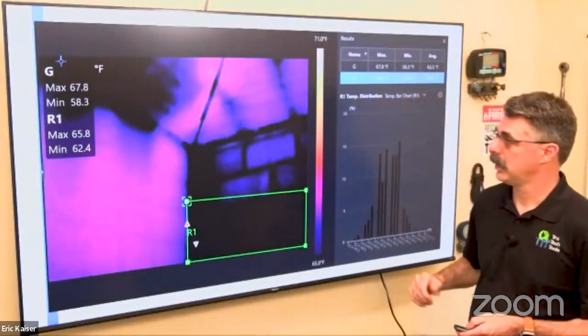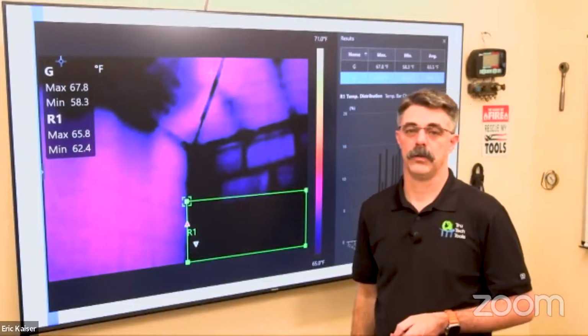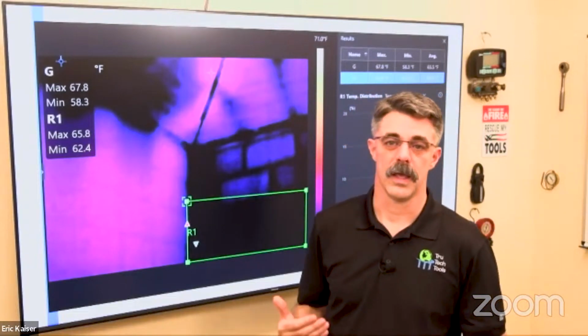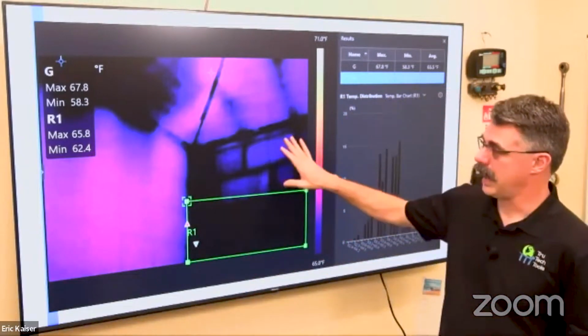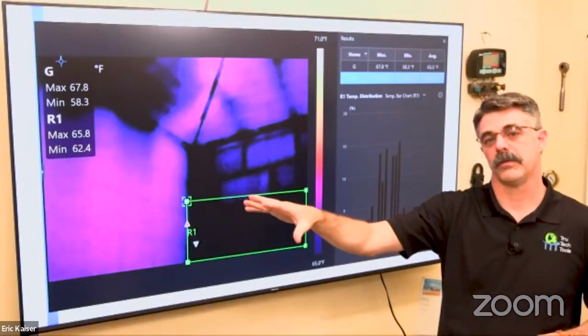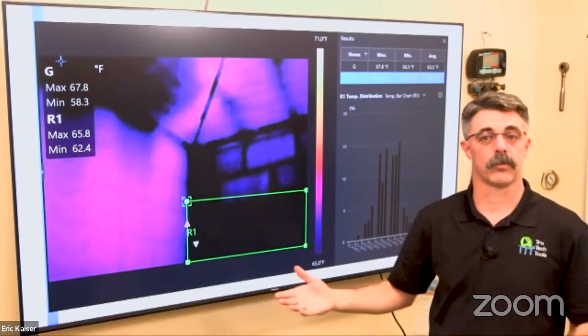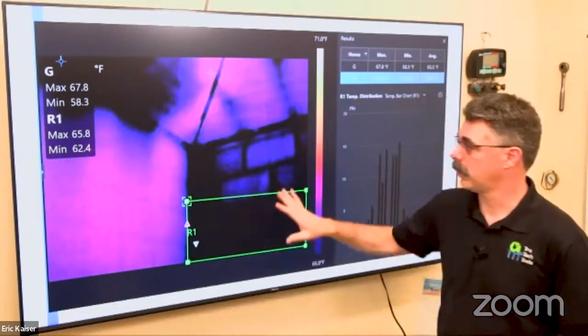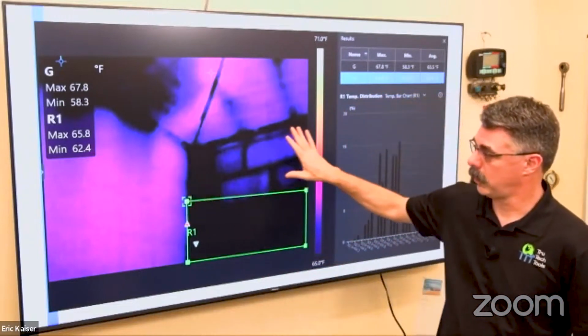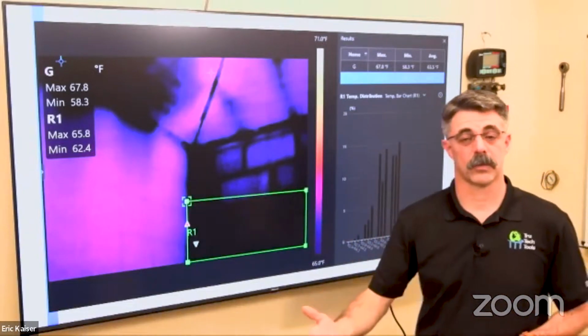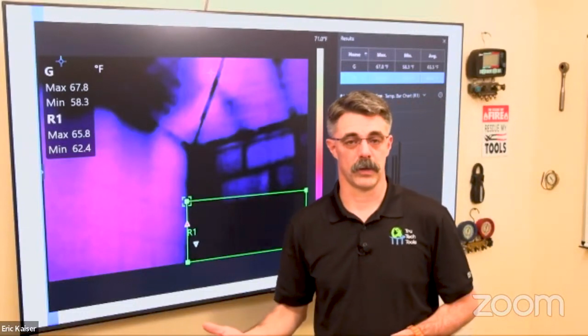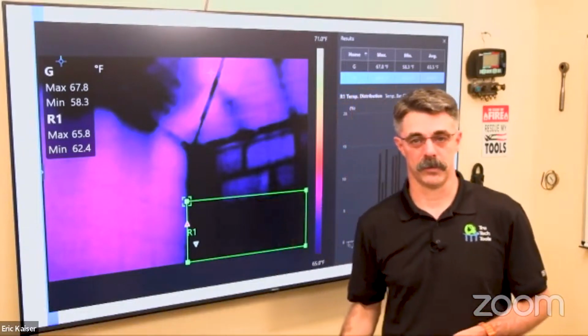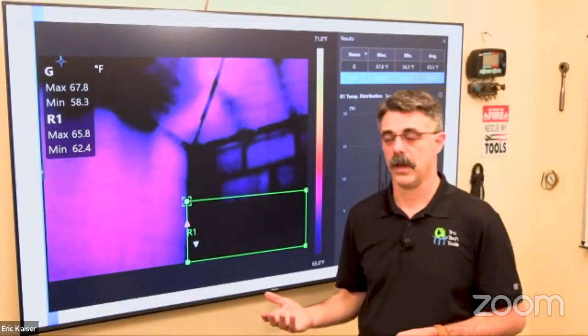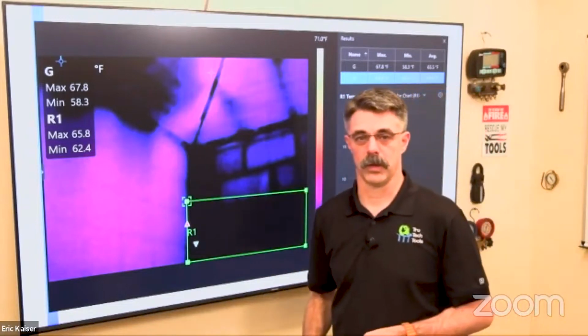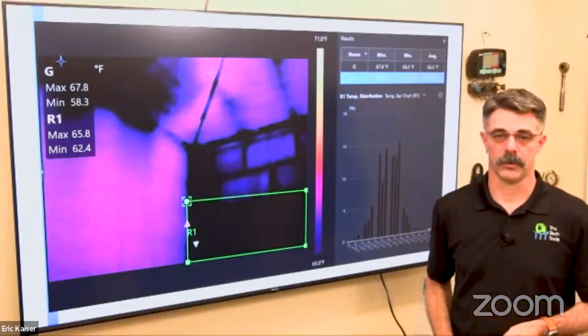Now, one of the other things is we can use a thermal camera to inspect the surfaces in the house. If we are there when the equipment is running, say in heating or cooling mode, we can actually go in and use a thermal camera to see what the distribution of that air is on the surfaces. If somebody's really uncomfortable in a certain area of their house, we go in there with a thermal camera and we start looking around and we can see hot spots and cold spots. Maybe it's right next to their chair that there's a really cold spot or a really hot spot. Maybe they're uncomfortable sitting in this one spot of their house or a certain room. And you can find those things with a thermal camera. So keep in mind that's a valuable tool for this process.